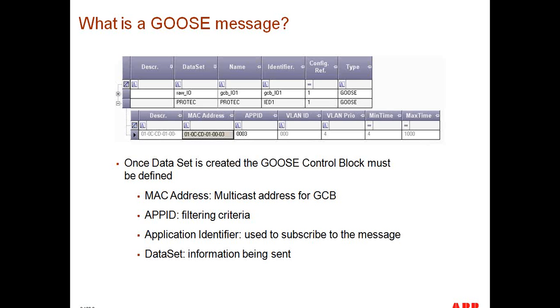Further, let's take a look at some other attributes of a Goose message. Addressing: we have a multicast MAC address for the Goose message. And here I would like to spend a couple of minutes to really explain this. When we discuss MAC addresses, it is true that physical devices, protective relays, computers, anything essentially that has a hardware Ethernet adapter has a unique MAC address that cannot be modified in most cases.